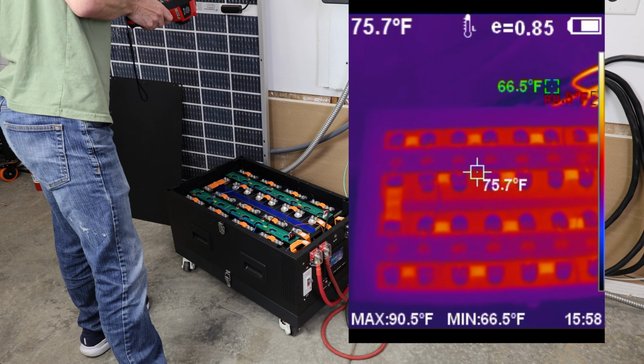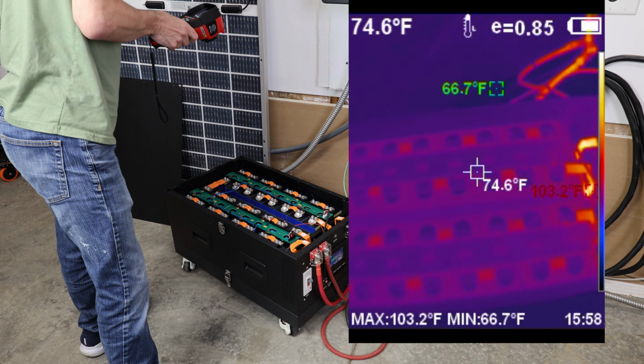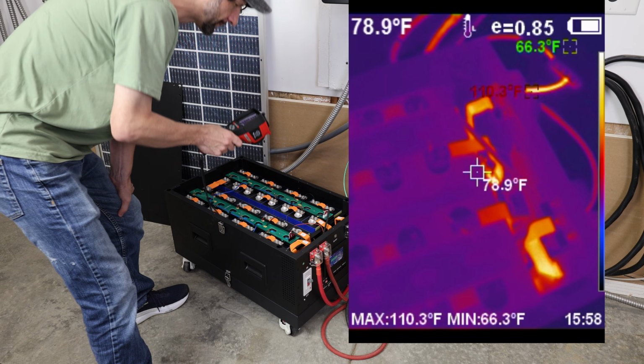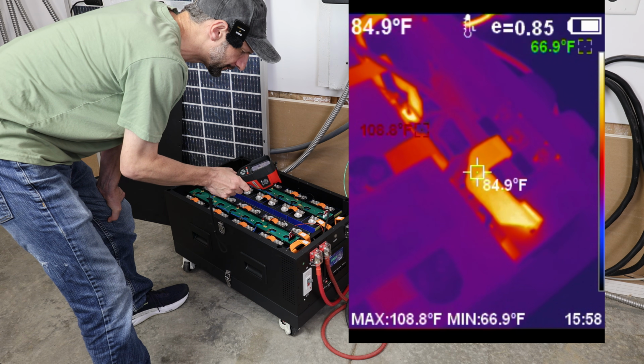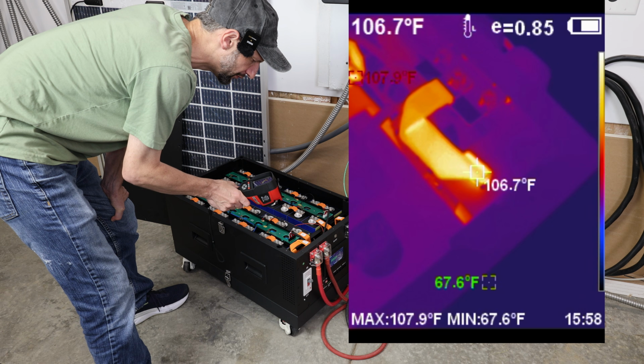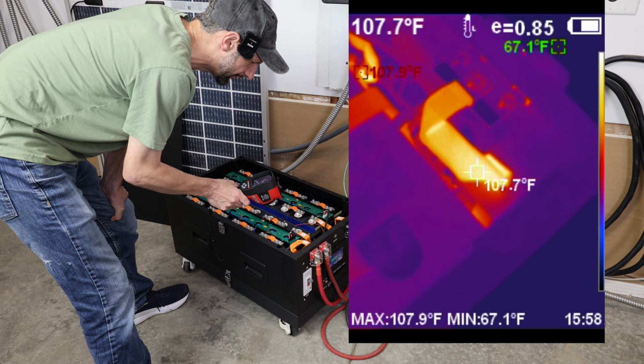Everything is a nice even temperature. There's no hot spots, so that tells me everything's been properly bolted. The hottest thing in here is the bus bars, and they're barely over 100 degrees.